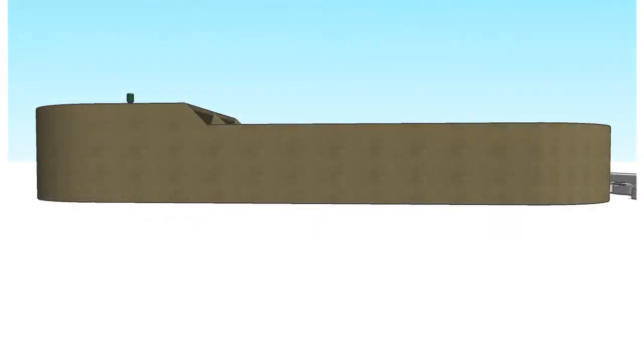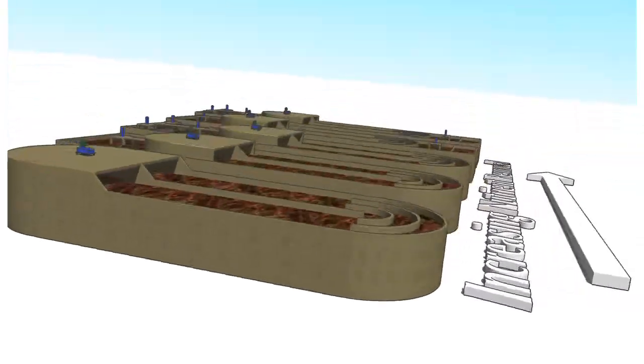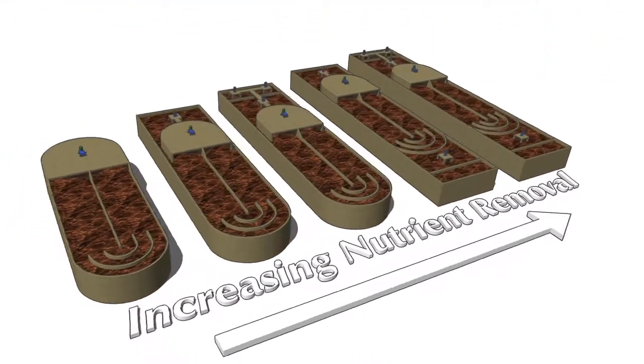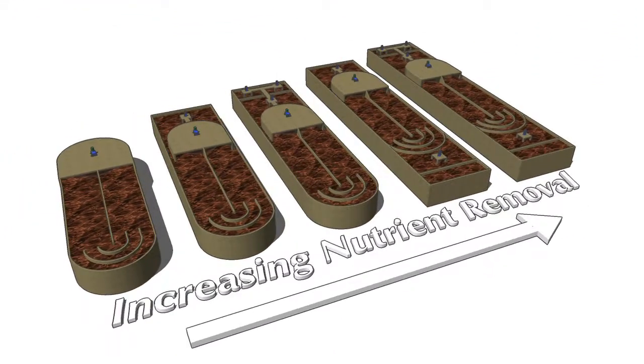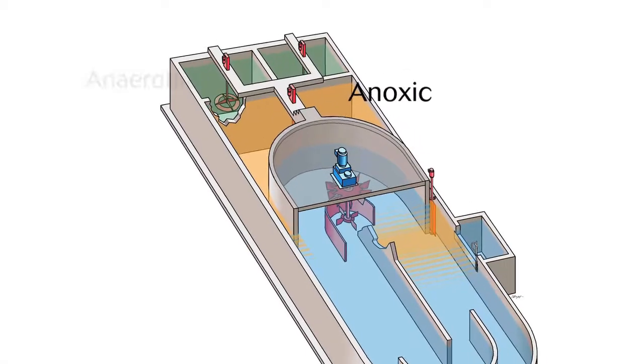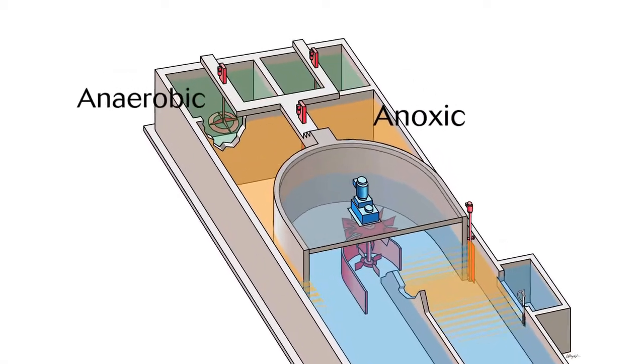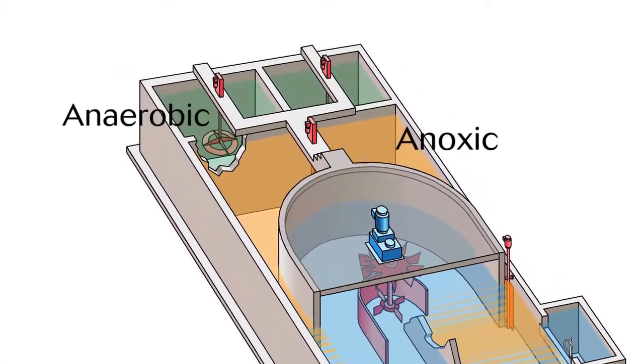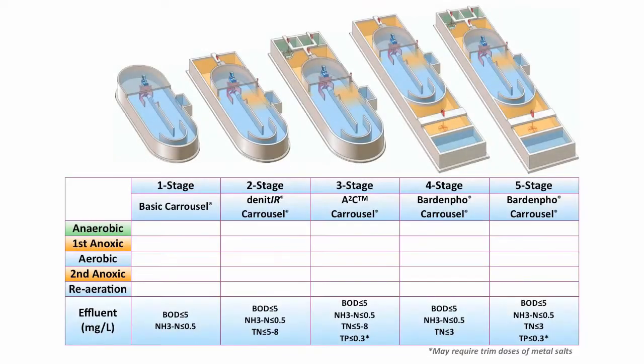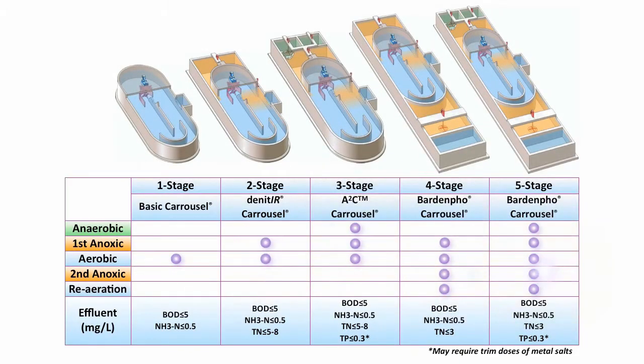The basic carousel process can be easily modified to biologically remove the nutrients nitrogen and phosphorus from the wastewater. By adding anoxic and/or anaerobic selector basins to the carousel system, 2, 3, 4, or 5 stage plants can be configured based on the effluent requirements.